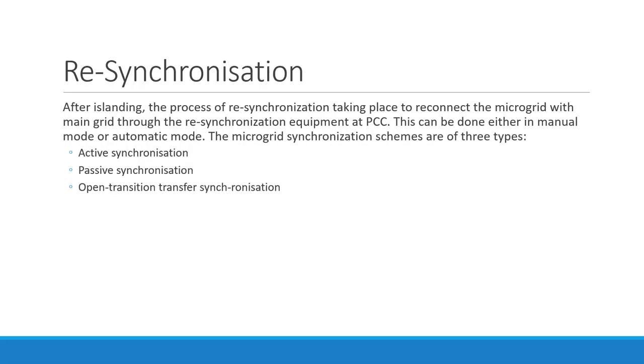Resynchronization is another issue with protection. After islanding, the process of resynchronization takes place in order to reconnect the microgrid with the main grid. This can be done either in manual mode or in automatic mode. For the microgrid synchronization scheme, there are three types: active synchronization, passive synchronization, and open transition transfer synchronization. So one possible method can be selected for resynchronization out of these.